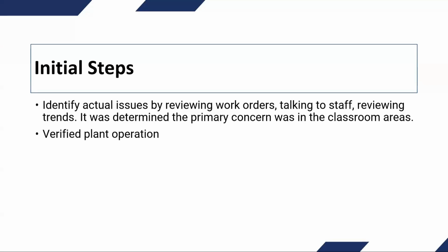So our next step was to go to the plant level. We took measurements at the plant, checked the chillers out, checked the pumps out, made sure everything was operating correctly, or at least determined a baseline of where everything was operating. We did the same thing with all the makeup air handling units. We traversed the units to get total flow. We measured GPMs and temperatures to determine a baseline for the makeup air units. We did a large sampling of the fan coil units, doing the same things, taking all the airflow measurements, temperatures, and GPM readings.